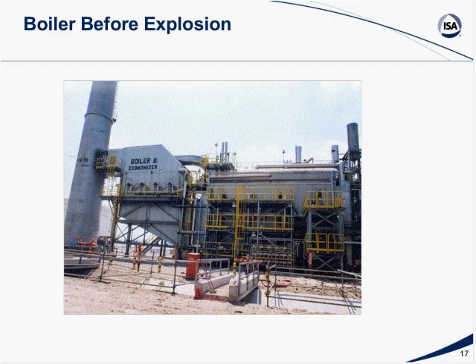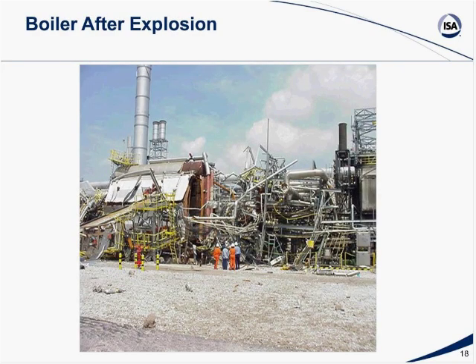They went and took the locks and pads off of the manual shut-off valves and opened those valves and opened the control valve. When they did, they got a very fuel-rich mixture going into the boiler, and the heat that was already in the boiler from the previous ignition caused an explosion. It did a tremendous amount of damage, as you can see in this next video. This next picture. Unfortunately, both of the operators were killed in this incident.